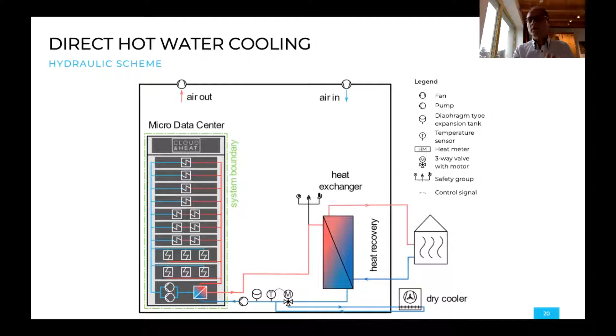Now, cooled down means, in our systems, the server needs a temperature of 55 degrees Celsius or lower, and that's cold enough to cool those servers. I'm talking about 55 degrees, so that's typically hot water, right? But 55 is cold enough with our technology to cool the servers. And the servers heat up this water from 55 to 60 or even higher. And this 60 degrees Celsius is hot enough, right, to be used in a lot of applications and not to be considered as waste heat. If you have just warm air coming from a server, that has literally no value. You want to get rid of that, right? But if you have really hot water coming from the server, it suddenly begins to have a value because you can use it for other things.